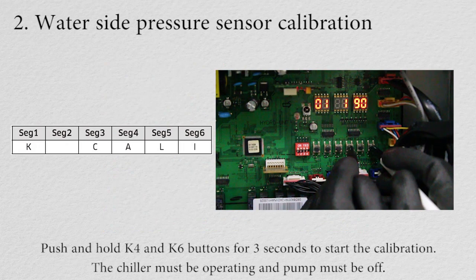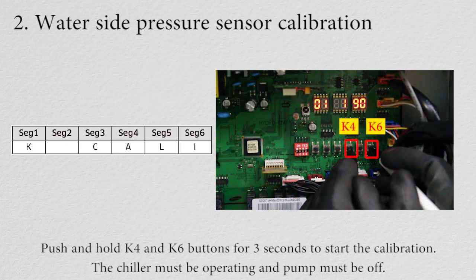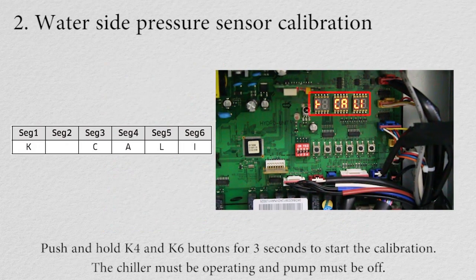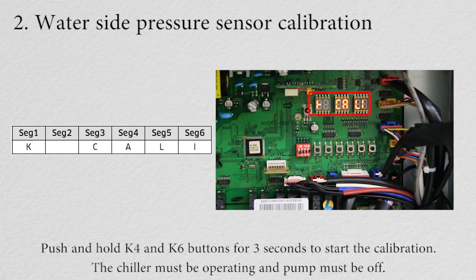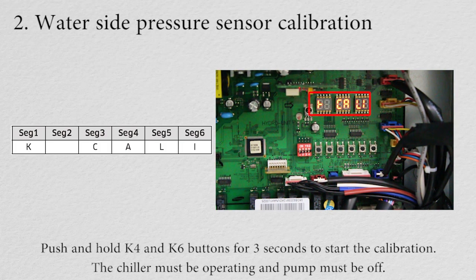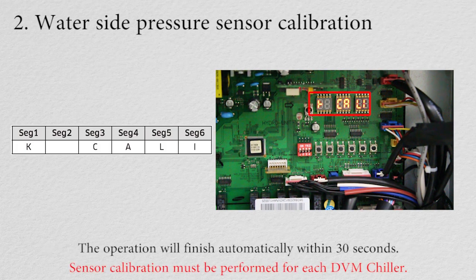Let's review how to perform the calibration. Push and hold the K4 and K6 buttons for 3 seconds to start the calibration. The chiller must be operating and the pump must be off. The operation will finish automatically within 30 seconds. Sensor calibration must be performed for each DVM chiller.